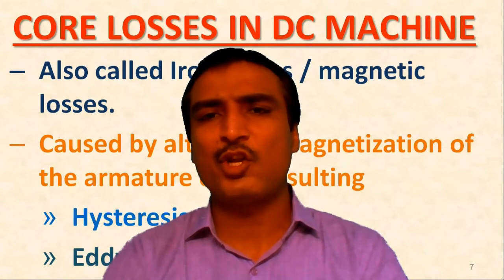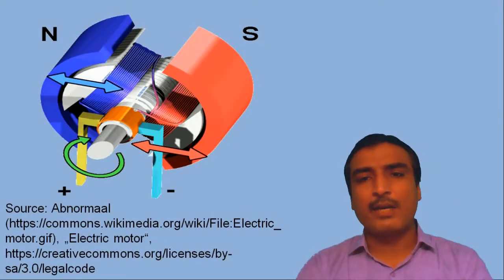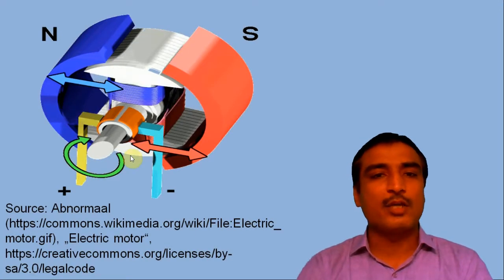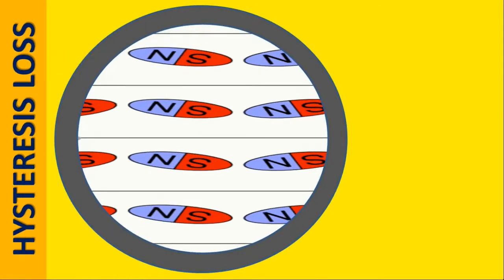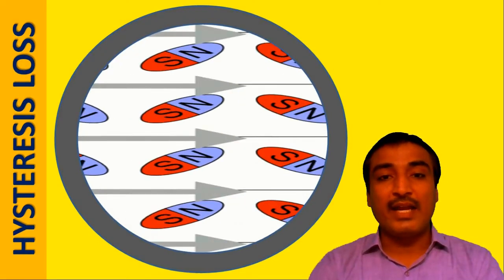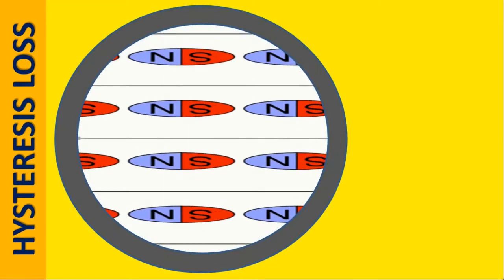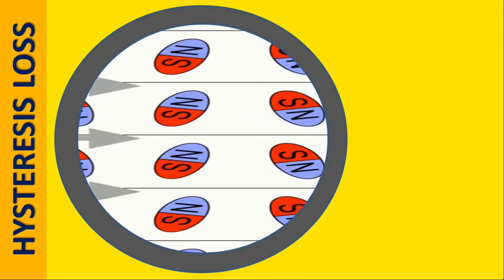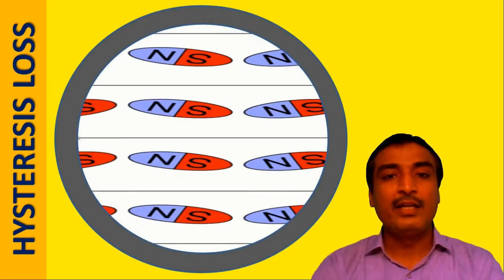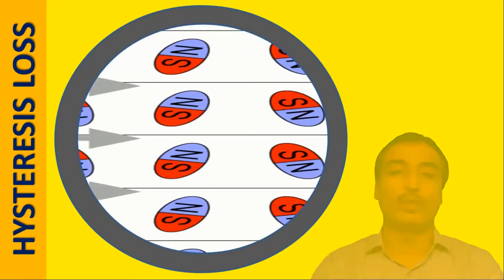The first question is how does hysteresis loss occur in the armature core of a DC machine? In reality, when any particular segment of the armature core passes under successive north and south poles due to the rotation of the armature, the magnetic domains in that segment of the armature core material are subjected to magnetic field reversals. As we know, the domains in any magnetic material have a tendency to align themselves in the direction of the magnetic field. For that reason, with the rotation of the armature in the magnetic field, the magnetic domains in the armature core material start rotating to and fro. Consequently, some power is wasted on account of the to-and-fro rotation of the magnetic domains in the armature core.